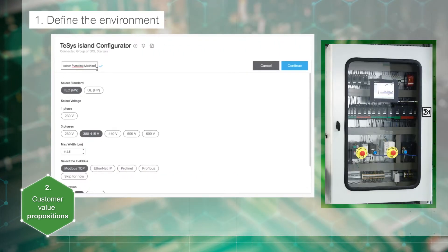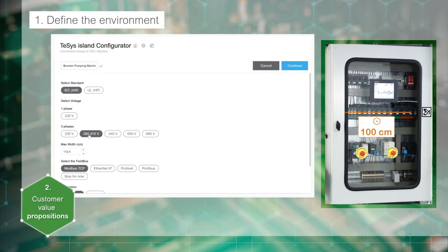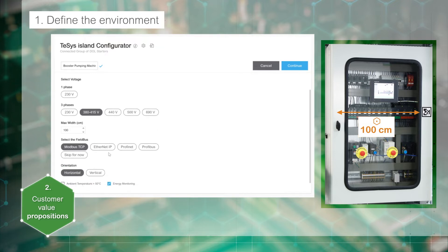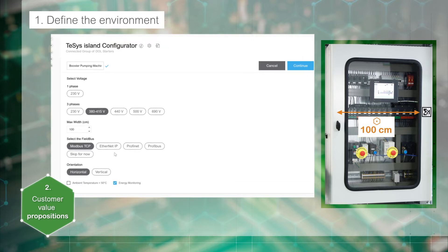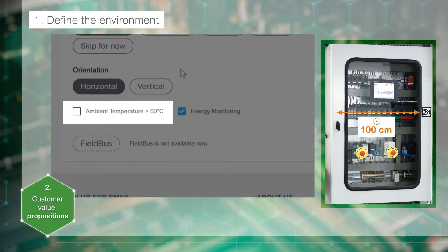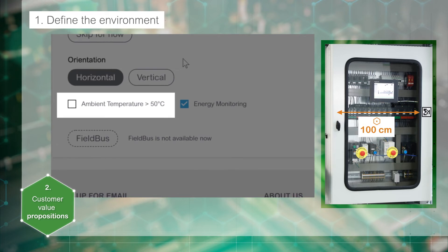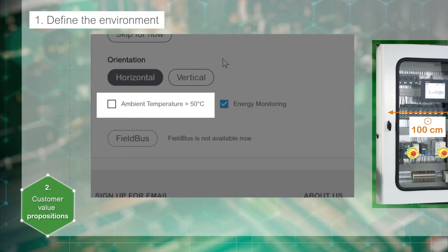Step 1: Name your configuration. Define the island environment such as power supply voltage, cabinet space and orientation, communication protocol, ambient temperature. Derating is automatically calculated when ambient temperature is above 50 degrees Celsius and/or vertical orientation are selected.